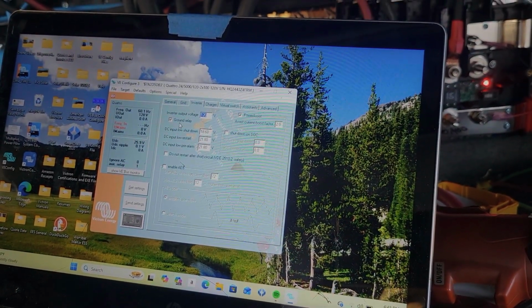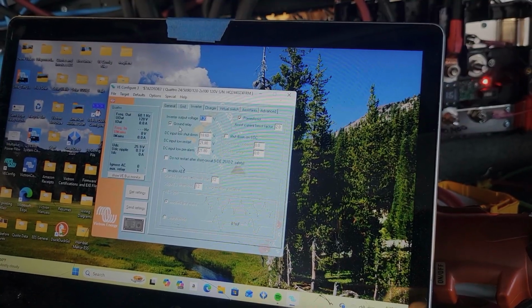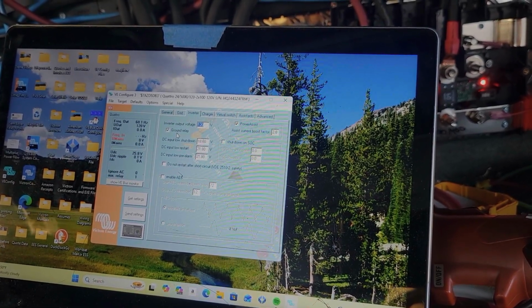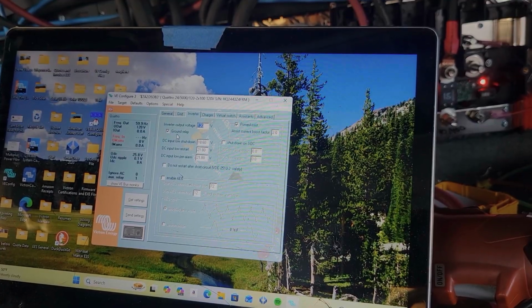Right. So typically that would be on an off-grid system or different systems. That would be the authority having jurisdiction would tell us when and how he wants the ground relay. And they can make the choice. I only want the neutral ground bond to be done at the main panel. I don't want your inverters to do it.